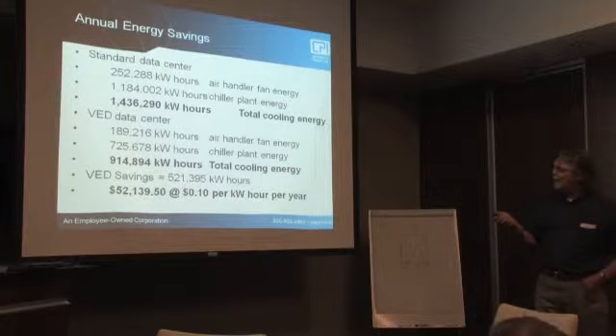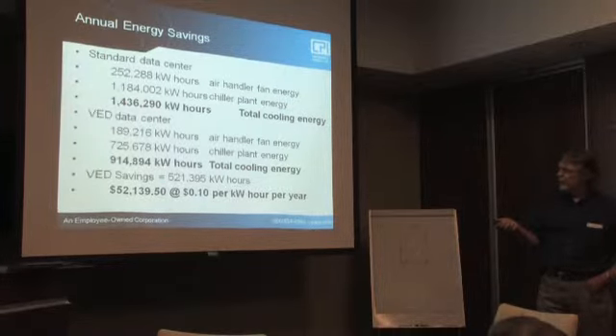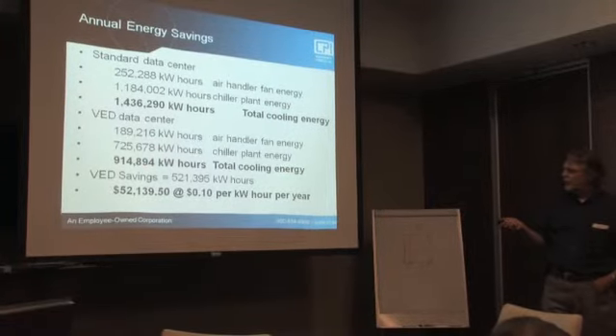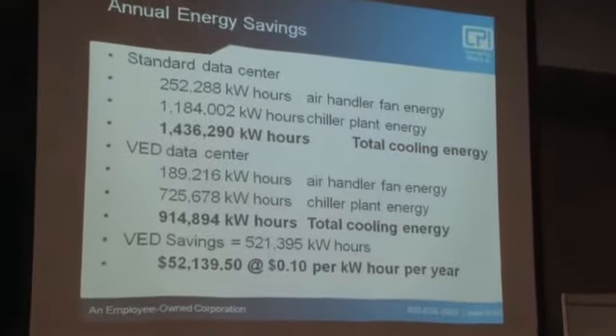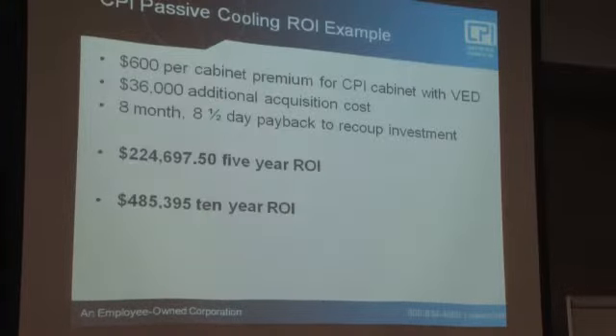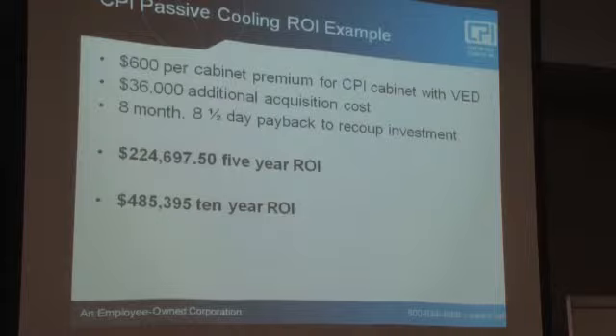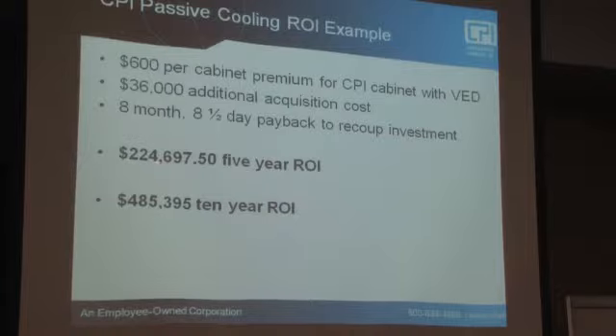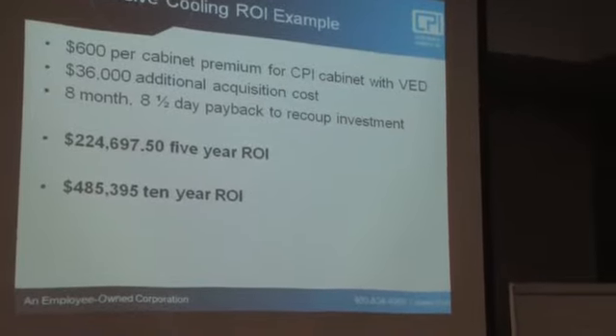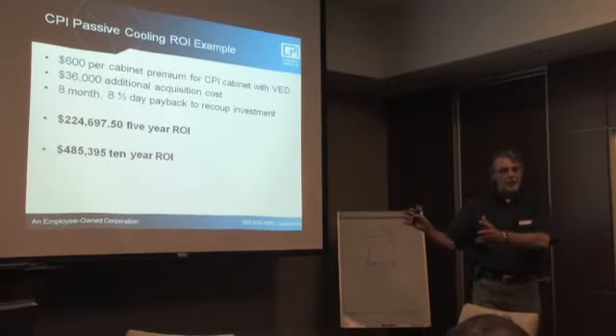The standard data center total energy is 1,400,000 kWh versus the VED data center at 914,000 kWh — saving $52,000 per year at 10 cents per kWh. Using a $600 price delta versus a non-chimney solution gives an extra $36,000 in acquisition cost, which pays back in about eight and a half months. Over five years the ROI is $224,000, and over ten years it's $485,000.